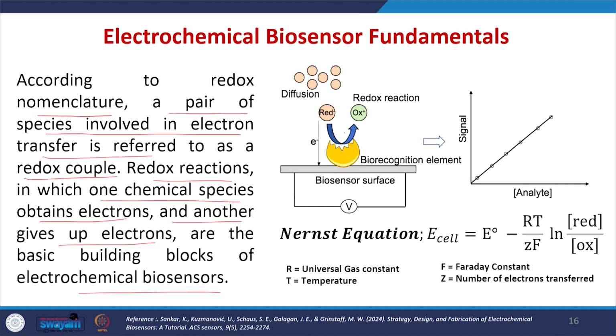In this picture, you can see the target analyte undergoes diffusion to reach the biorecognition element, which is immobilized on the biosensor surface. The biorecognition element specifically interacts with the target analyte, triggering a change in the redox reaction. This reaction generates a flow of electrons, which is then captured and translated into an electrical signal by the transducer. The magnitude of this signal is directly proportional to the concentration of the analyte, as shown in this graph.